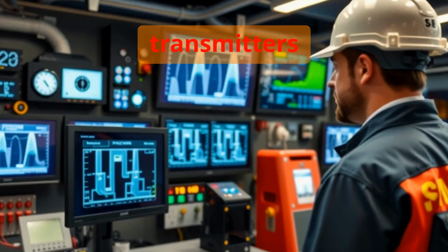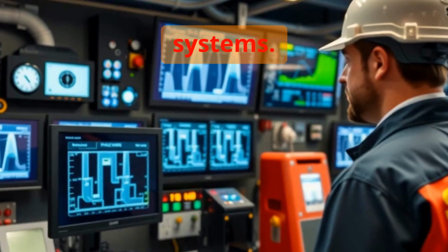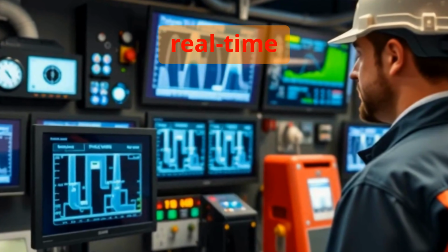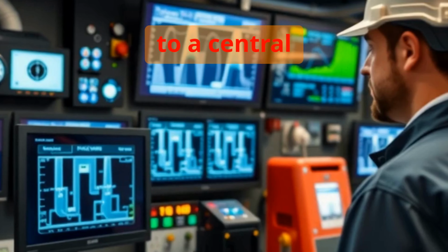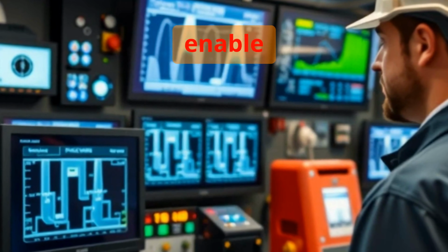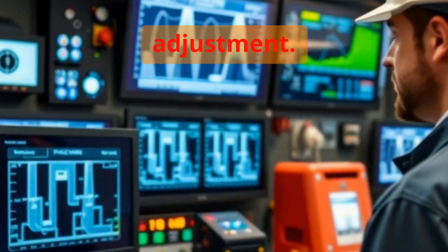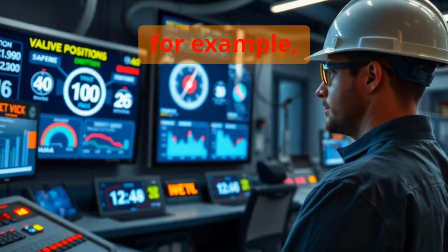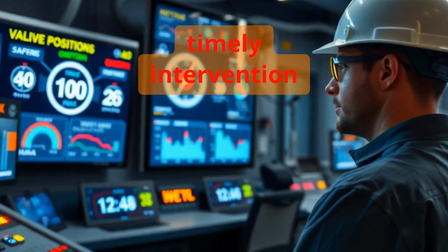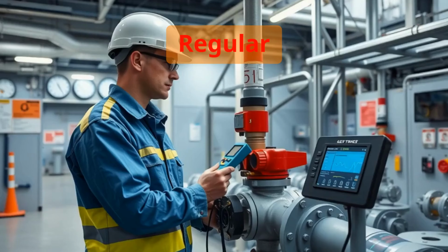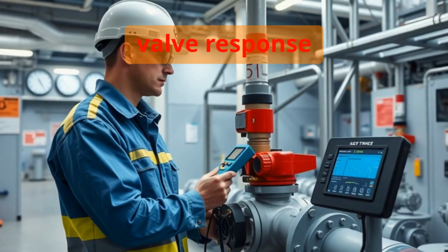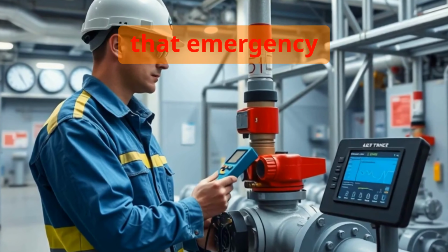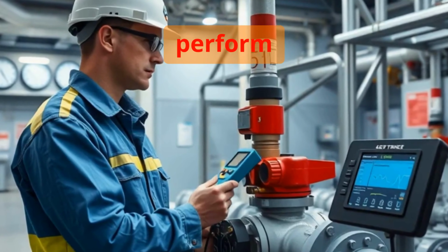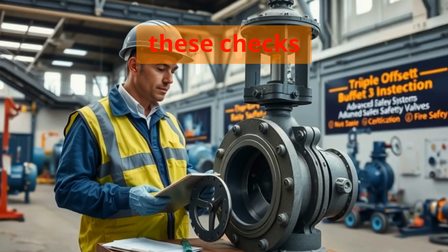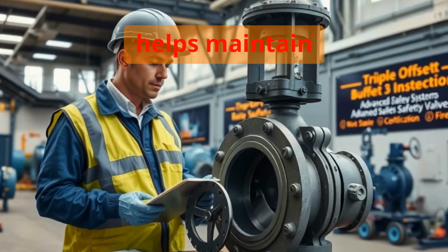Position feedback transmitters are key components in modern control systems. By sending real-time data about the valve's position to a central controller, these devices enable precise monitoring and adjustment. Detecting a lag in valve opening, for example, allows for timely intervention before process issues arise. Regular testing, such as the ESD valve response check, ensures that emergency shutdown valves will perform when needed. Completing these checks on a quarterly basis helps maintain safety and compliance with regulatory requirements.